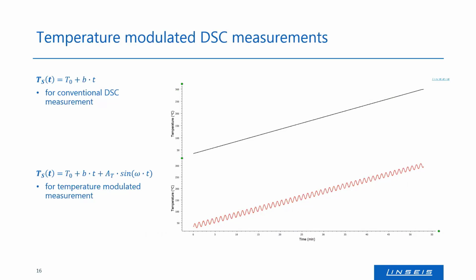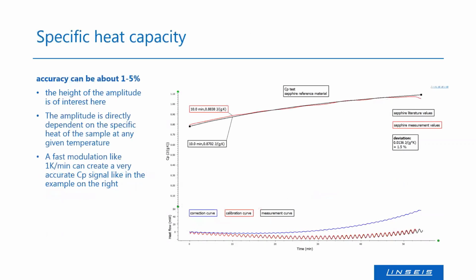By the way, the omega here is of course the period of our modulation, important to know. So okay, through this temperature modulation we could get some results. I've checked it with our chip DSC and the results are quite good. What I've tested here is just the zero curve you can see here in blue at the bottom of this diagram, and then also the calibration curve and the measurement curve. Both of these materials are sapphire, so they are basically the same.